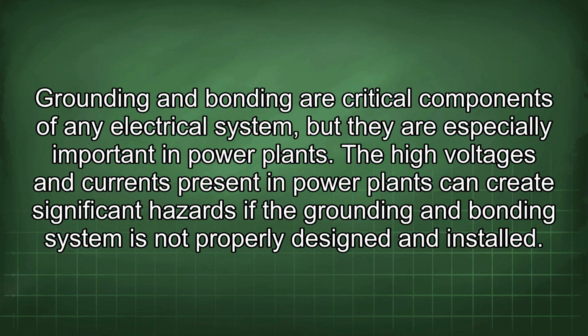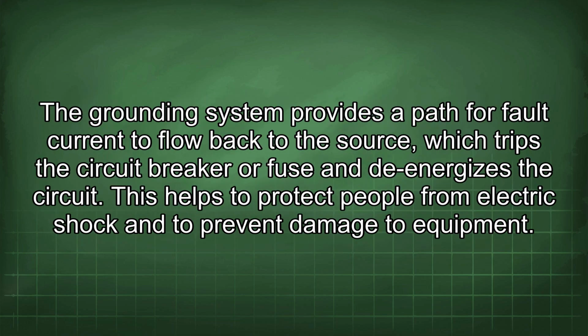Grounding and bonding are critical components of any electrical system, but they are especially important in power plants. The high voltages and currents present in power plants can create significant hazards if the grounding and bonding system is not properly designed and installed. The grounding system provides a path for fault current to flow back to the source, which trips the circuit breaker or fuse and de-energizes the circuit. This helps to protect people from electric shock and to prevent damage to equipment.